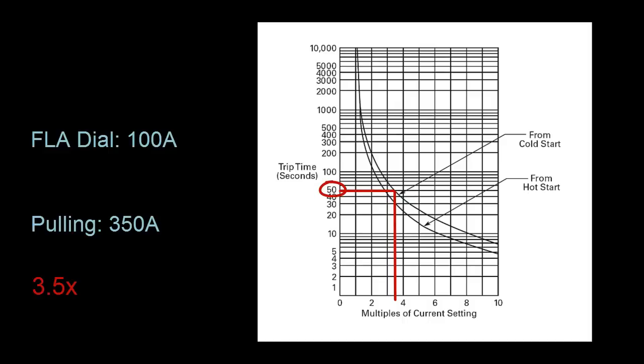By the way, a hot start is when the motor was started again after it had been running for a while beforehand. It's going to trip more quickly in an overload condition in this case because there is already some amount of heat in the bimetallic strip.